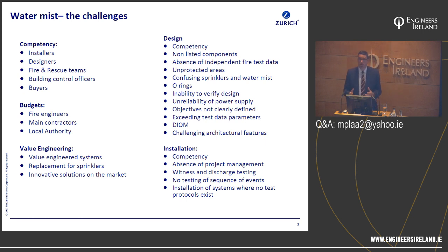And buyers can often be attracted by the lower cost of water mist, and there are some really great examples of where water mist is a really good tool in the toolbox of the fire protection engineer, and I've come across many such examples and recommended water mist. But we also have to be careful, as a note of caution, that buyers can often be attracted by the lower price than sprinklers, but are we comparing apples with apples? And often we're not. We're comparing apples with pears, and often, especially for the land-based market, we can be looking at water mist being promoted to us as being cheaper than sprinklers.